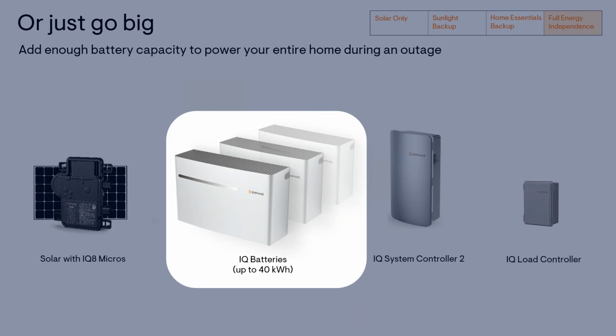For larger homes that have split buses, for example, like a 400 amp or 800 amp split bus, they can actually have 2 systems installed. So they would have 2 system controllers with batteries and solar connected to each one of them. They would essentially operate independently from each other. They don't share power or anything like that. But for homeowners that do require larger than 40 kilowatt hour systems and they have a split bus, they can have 2 separate systems.